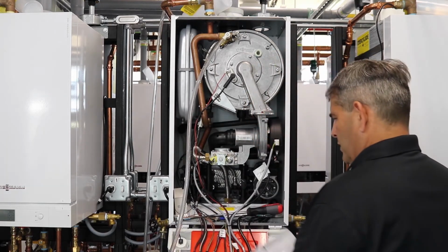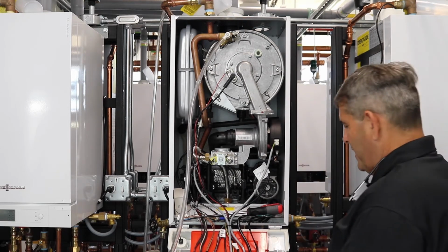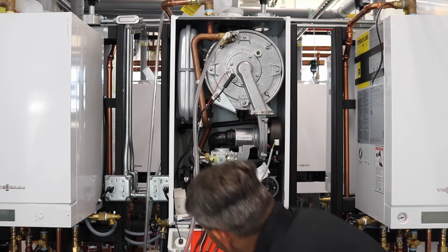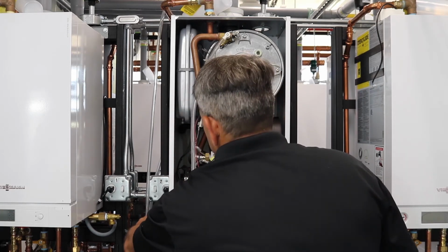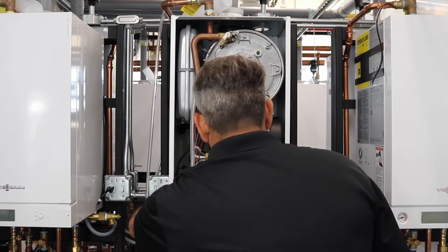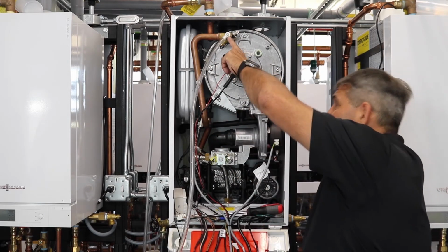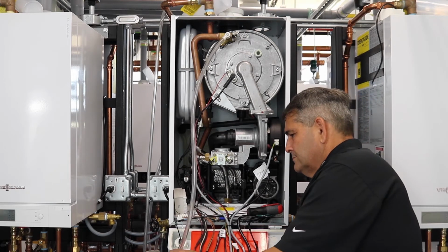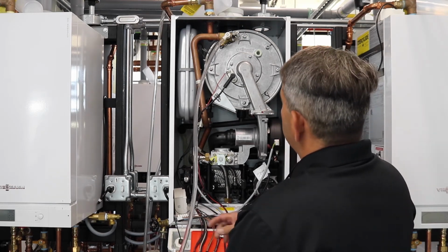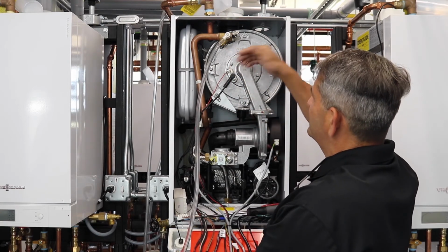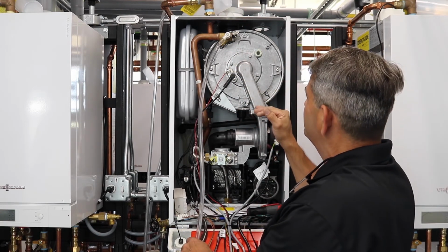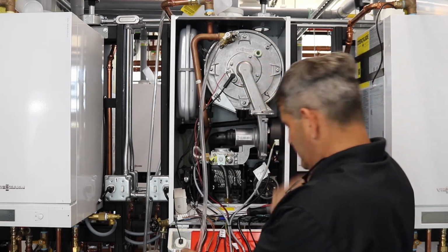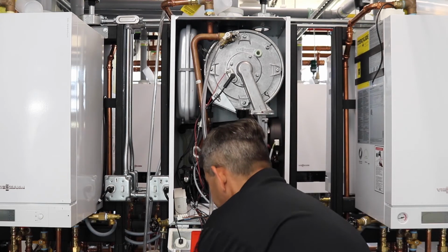And now we're going to purge our boiler to get all the water back into the system. What I like to do is fill the boiler with my bleeder open. And as you'll see, you'll get a few bursts of air because we didn't drain the boiler completely out. And now we're pretty much completely free of air, so we'll take our key and we'll shut that.